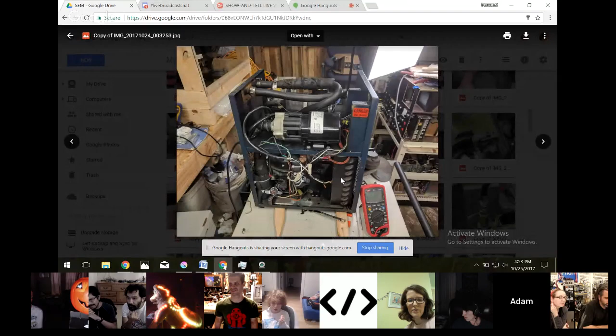So I'll show you what started to happen with that. This has basically been a comedy of errors this week. This is my water chiller, not what it normally looks like, and the fact that the lid's off should tell you something's horribly wrong with it. It started tripping my ground fault interruption circuit, which is disturbing when you know it's water.